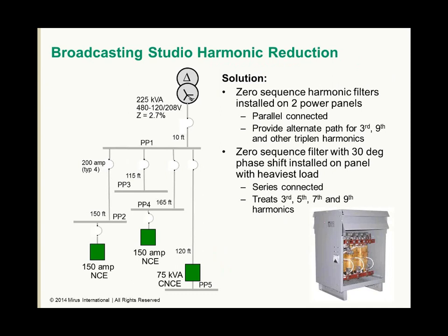We applied low zero sequence passive electromagnetic harmonic filters at 3 distribution panels at the site. Mirus invented these devices in the early 90s, and they have been very effectively used in many applications over the years. These devices provide an alternate low zero sequence path for the triplen harmonics to flow, while phase shifting to cancel 5th and 7th harmonics. So we use 2 parallel connected zero sequence filters and 1 series connected, which introduces the 30-degree phase shift to provide the cancellation of 5th and 7th.